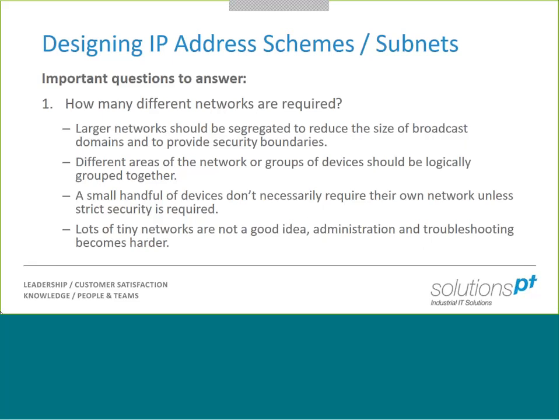And the same could be said for a server network. Perhaps we've got a SCADA or a Wonderware server estate with application servers, historians, that kind of thing. And again, that would be a good fit for its own network, because when we're talking about servers, we want to add a layer of security there. So having your servers in an isolated subnet, we've got some control over what can and can't access them. Again, that's another good scenario for a different network.